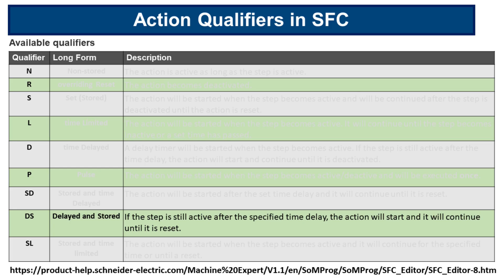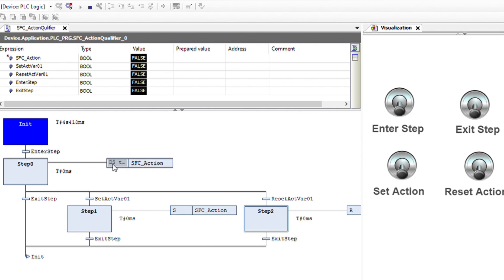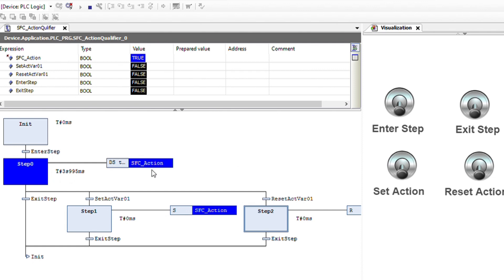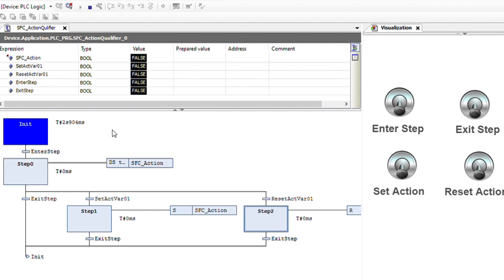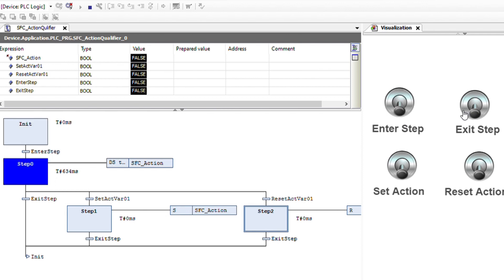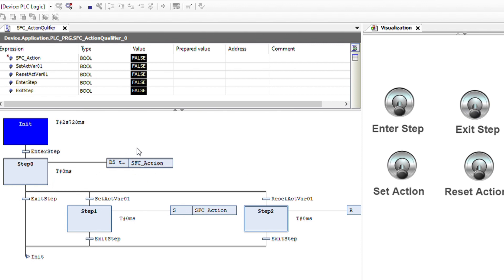The next action qualifier is DS, or delayed and stored. If the step is still active after the specified time delay, the action will start and it will continue until it is reset. In the case of DS, if we enter into the step and then leave before the time delay of 3 seconds has passed, the action will not be set. If we remain for 3 seconds, it is set, and then if we get out and come back nothing changes until we reset the action. Now entering and leaving before 3 seconds, we see that SFC action does not become true. That's the main difference between DS and SD: with SD the action is set 3 seconds after entering even if you leave, while with DS it only sets if you are still in the step.